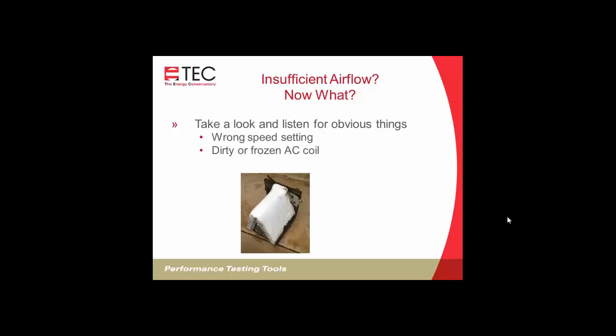Maybe a dirty or frozen air conditioning coil. That can certainly be an issue, and we'll talk about, if you measure the pressure across the coil, what numbers are good numbers, and what numbers are bad numbers.